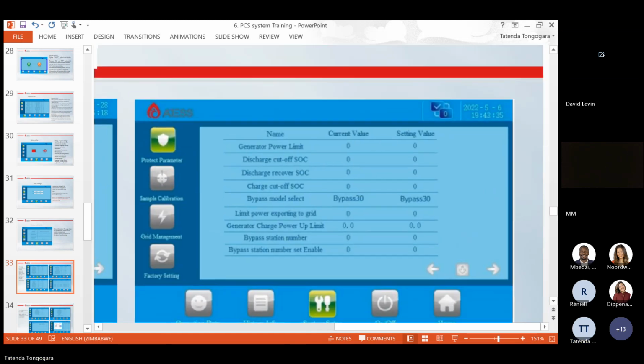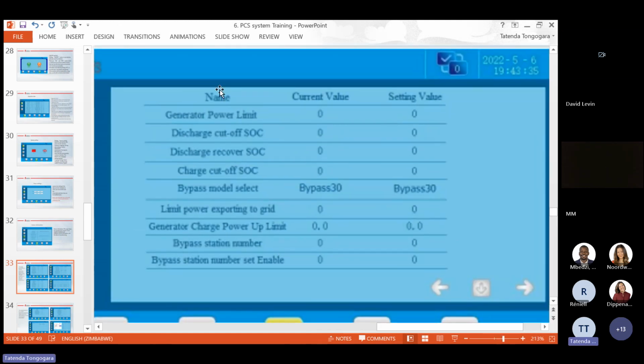So these are the parameter pages on the PCS. They are the same as on the HPS. The only difference is on this page. On the HPS, you have your ATS, the bypass model. So if it's PCS 500 with bypass 500, it should show bypass 500 here. Or if you are using bypass 1000 on PCS 500, it should also show bypass 1000 here. Limit power exporting to grid.